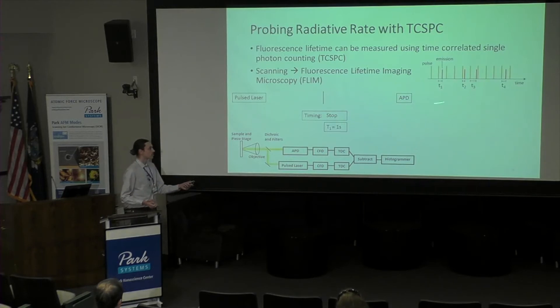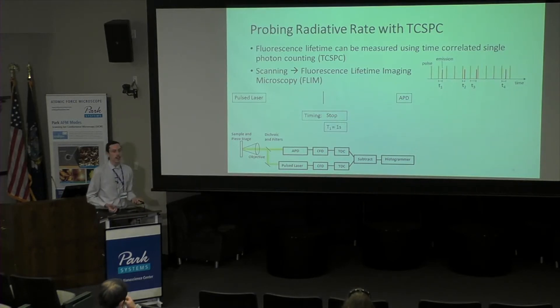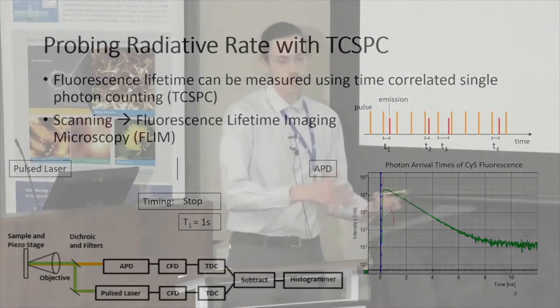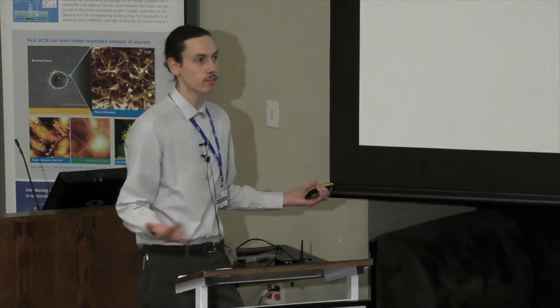Based on the delay between excitation and emission, you get a fluorescence lifetime. You collect a number of these delay times over time, histogram them, and from that you get a decay curve. By fitting this with an exponential, you can determine the fluorescence lifetime of your sample. By synchronizing this with a scanning piezo stage, you can look at the fluorescence lifetime at each pixel in a 2D grid and assemble an image of the fluorescence lifetime and how it fluctuates depending on your sample.